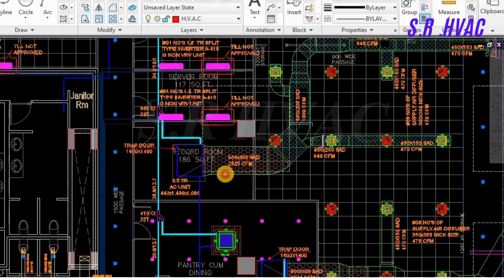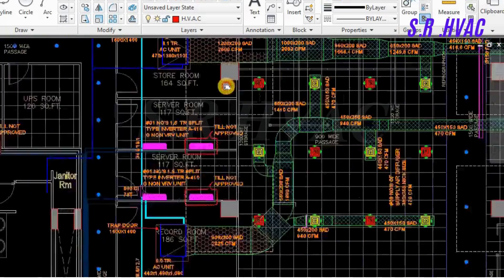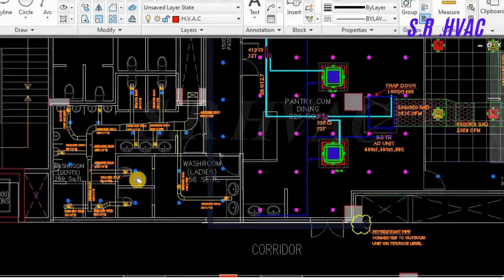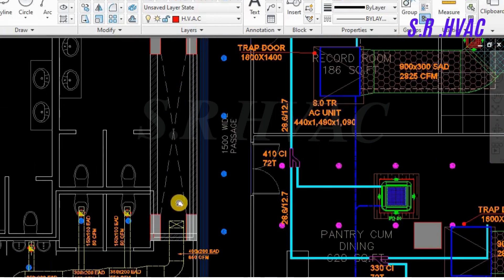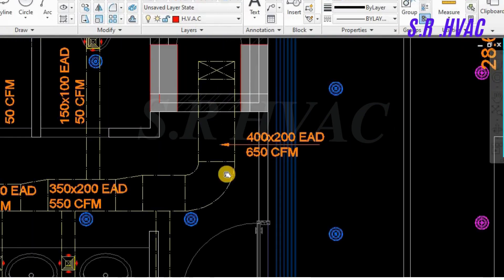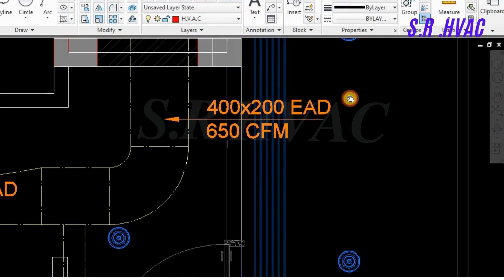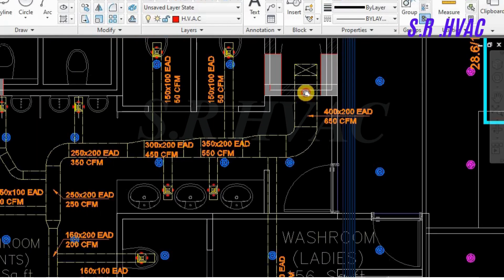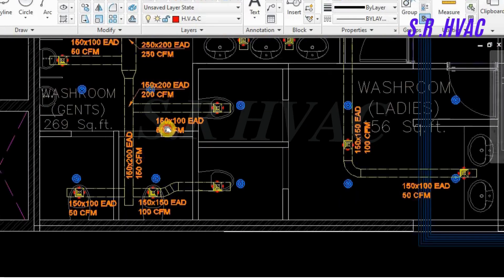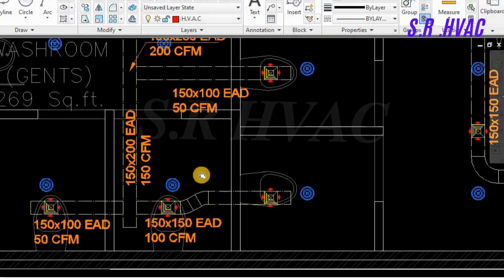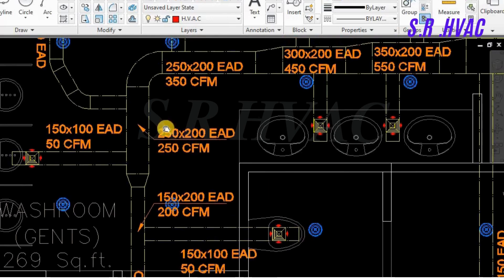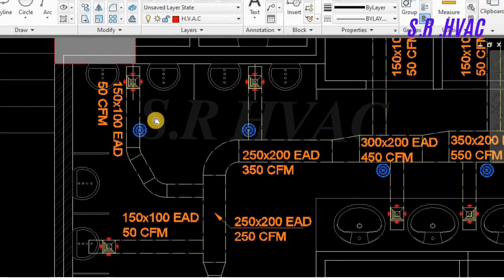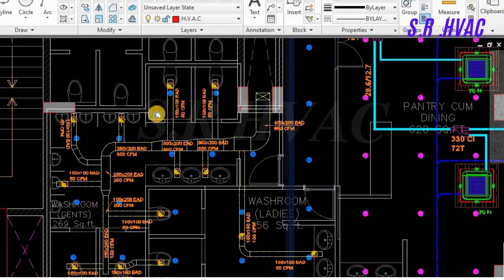So friend, this is fresh air duct. Now we are going to see our exhaust air. You can see from here this is open to sky. And this is connected with the fan and the CFM is 650 CFM. EAD, this term also you should know, this is exhaust air duct. The CFM is 650. It is coming from the terrace level, and it is going to all our wash area, as well as urinal. This is giving 50 CFM, this is 100 CFM, this is again 50 CFM, and this is also 50, 50.